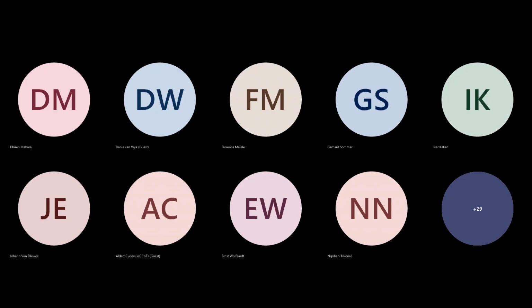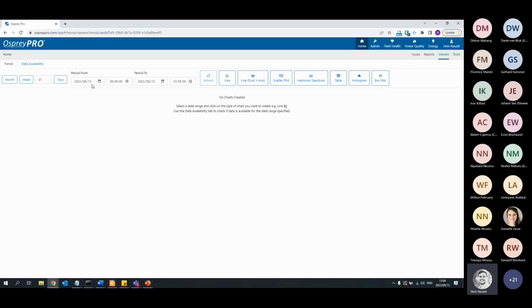So, Carl, I think the short answer is there's no quick way to do it, but all the data required is available as a CSV export. So you could do a 10-minute trend or a 3-second trend or whatever you've enabled on your Vector. And then you could pull the specific harmonics you're interested in. From the export, you just mask it over the time when it's sunshine out.